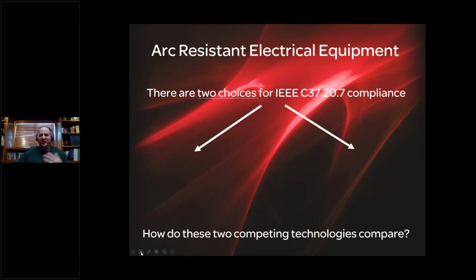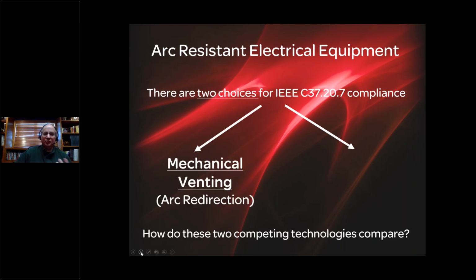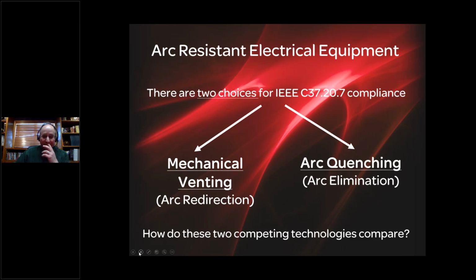So with respect to arc-resistant equipment, and many of you have seen this slide from one of my previous presentations, there are two choices and two choices alone for IEEE C37.20.7 compliance. The first is mechanical venting. We're going to build a very robust structure, an enclosure, and then redirect or vent the arc flash plasma out the top of the gear and attach plenums frequently to that, so out the roof of the building or side of the building where it's not going to hurt anybody. The second option, and the one promoted by L3 and my own company, and a central purpose of my presentation, is arc quenching. And I'll be upfront, I believe in every measurement of the two technologies, arc quenching obsoletes and is a superior technology to a mechanical venting solution for arc resistant compliance.